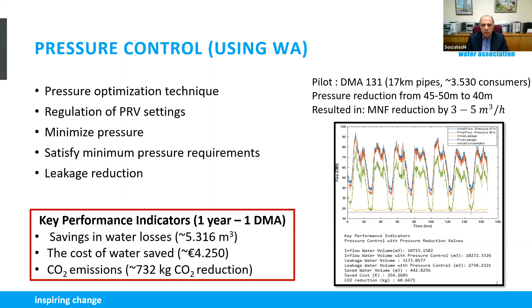After evaluating the results of this method using the digital twin, the proposed method was applied in the physical system. Using the controllable pressure reduction valve, which was installed at DMA 131, we reduced the pressure to the same levels as with the digital model, from approximately 50 to 40 meters. This resulted in a reduction of the minimum night flow by 3 to 5 cubic meters per hour, which is close to what the model predicted. The figure shows the real inlet pressure and flow measurements of DMA 131 retrieved from the SCADA system at the time of the pressure reduction application, shown by the blue vertical line.